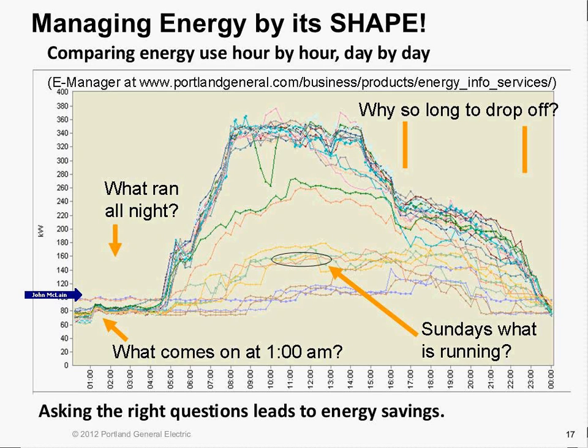with no one using them. What they did is they bought software, turned the computers off, and so now this graph dropped down and then started going up. So they saved all this energy in here, and they could graphically show the change in the shape after they'd made the change. So if you're asking for money to make changes, graphs are a good way to show the before and after and actually see the change, rather than bringing in this monster spreadsheet and saying, look, the data changed. So we find graphics a great way to not only ask good questions, but show results of changes.